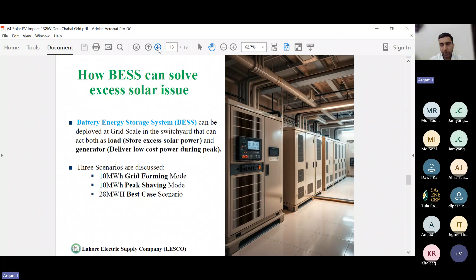If we look at the grid forming mode, we have this result from the simulation. We have this power flow curve, where we see that during the day hours it dips down to reverse, and this energy is basically going back from the rooftop to the substation. So we can install this battery at a substation and store this energy into the battery energy storage system during the day hours. This is a 10 megawatt hour battery energy storage system, and it can supply the same energy during the peak demand hours, in the evening and night.